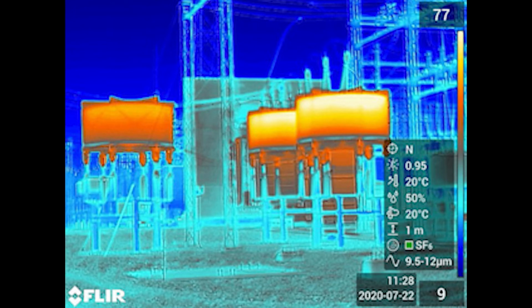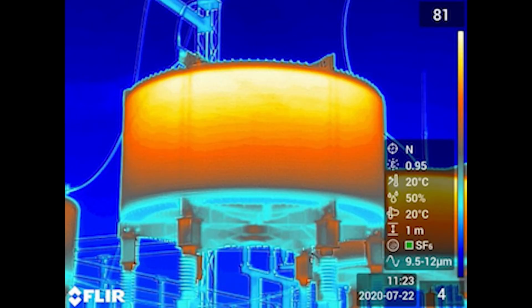We had the operator check the load on each reactor, and they were all loaded relatively equally. There is about a 20-degree differential between them. Not a cause for concern, but the operator will monitor them, and we will document the difference and compare this baseline image with future images to determine if a problem develops. Here you can see this is one of the newer reactors, and we got down, took a look at it, and we are trying to find any hotspots, any anomalies, anything that seems to be out of the norm. It seems to be working properly, and this coil seems to be operating within parameters.